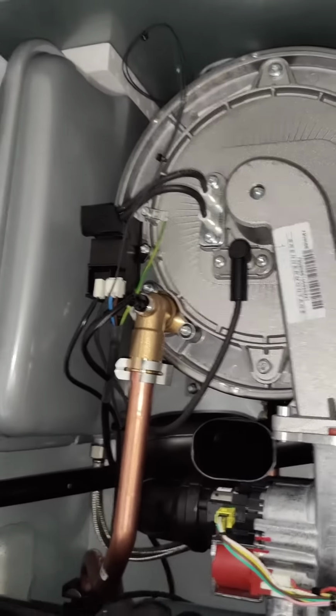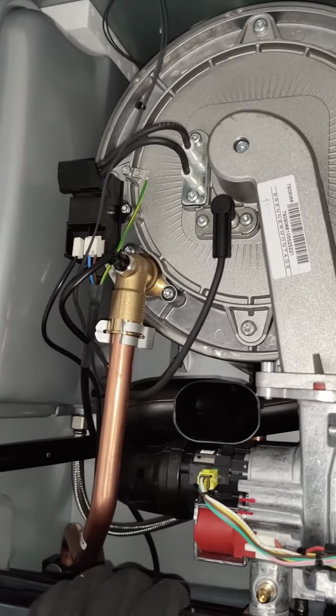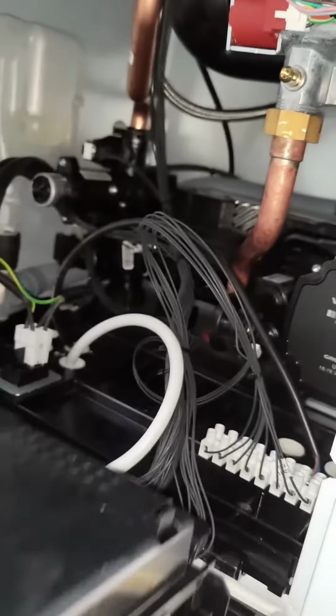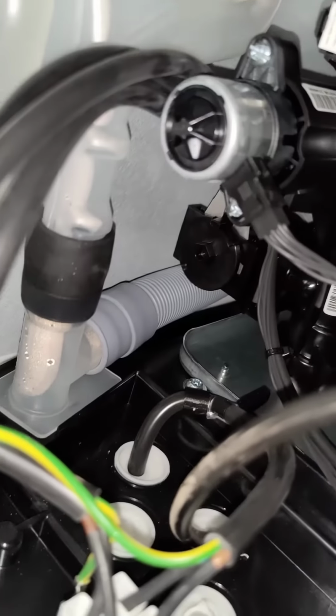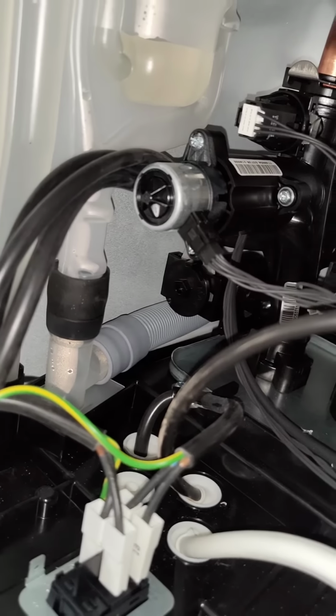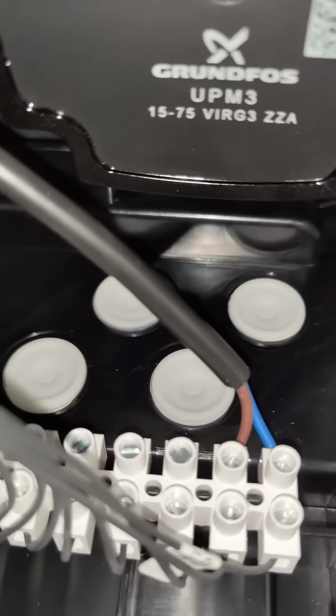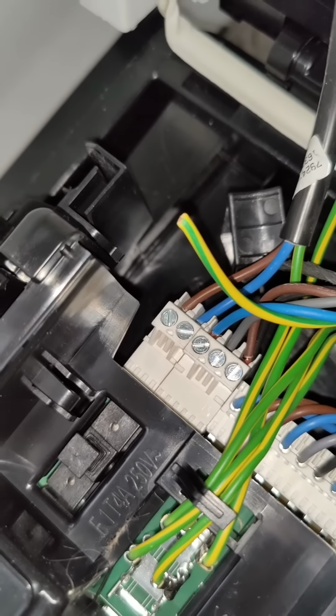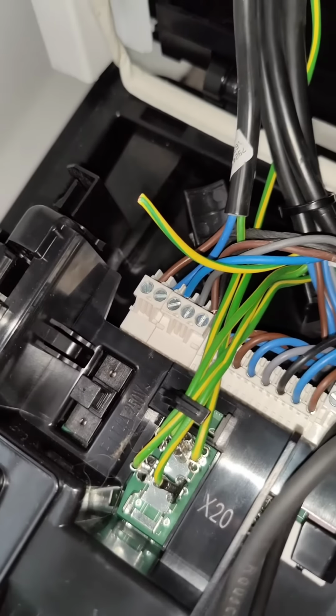Stainless steel heat exchanger. Apparently it's one grade down from medical steel, so it's about the best stainless steel you'll find in the boiler. We've got a modulating pump there. You've got the PRV, which connects straight into the condense trap, so we don't have to do a separate pipe for the PRV. You've got these two connections on the end for the weather sensor, and then here is the PCB. And on the second plug is where you can wire in the external controls. So if you've got a room stat, they can go into that second plug there.